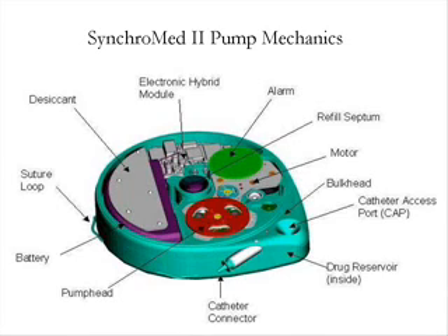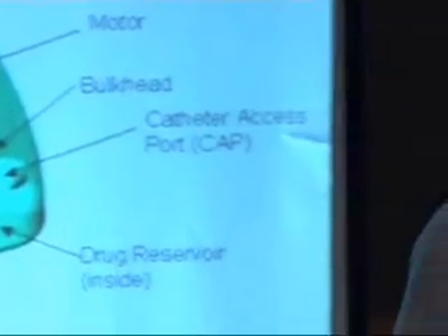You can see the rotor head here, the pump head, which has internal tubing. The actual reservoir is below that, and I think probably the most relevant aspect for you to know is that when we try and refill pumps, we're actually trying to hit this refill septum, which is right in the middle of the pump. You can see how small that target is relative to the size of the pump. The sample pumps that are being passed around, I think they don't have a septum. One of them does. And so you can get a sense for why it's really important that we align this template that we use for refills the correct way to be able to access that.